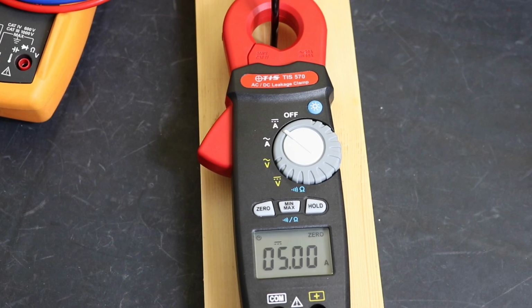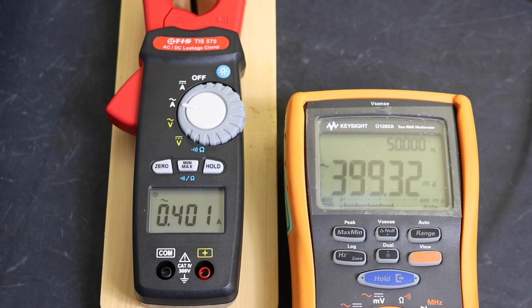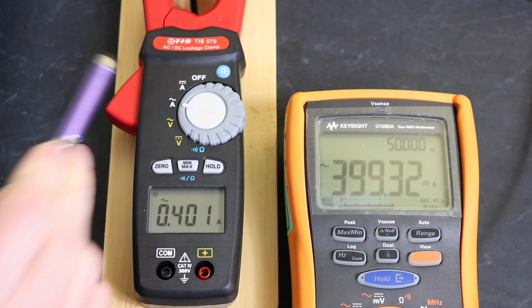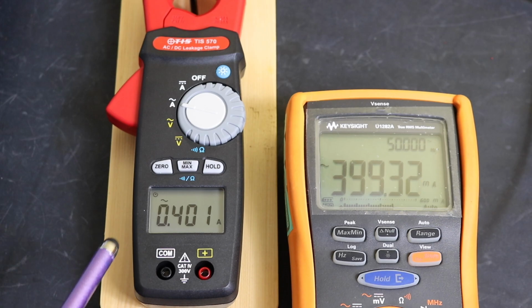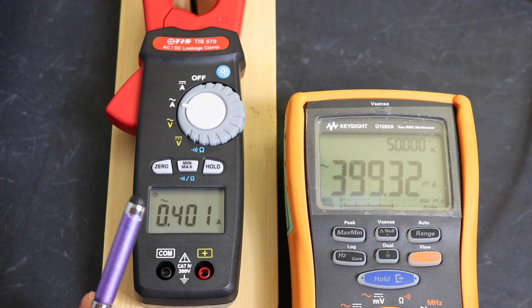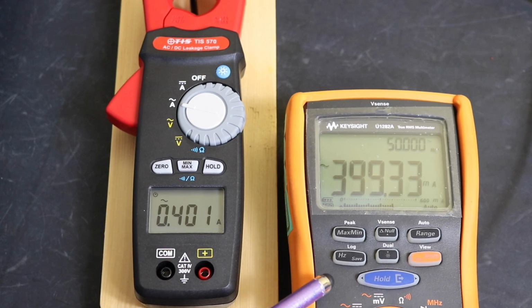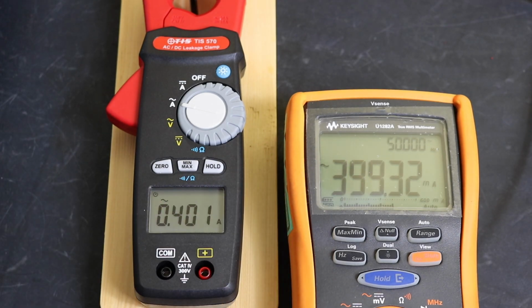What I'm going to do, I can do milliamps with the SMRT, but it's not very stable below 100 milliamps really. So what I'm going to do is just shut this all down and set up a different test set to verify the milliamps capability measurement of the instrument. So we're now set up with our test unit, and we are back injecting AC current. As you can see there, we are on 0.4 amps is our setting, 400 milliamps. You can see we've got 0.401 displayed on our TIS570, and on our Keysight we are 399.3 milliamps, and you can see the 50 hertz up there.